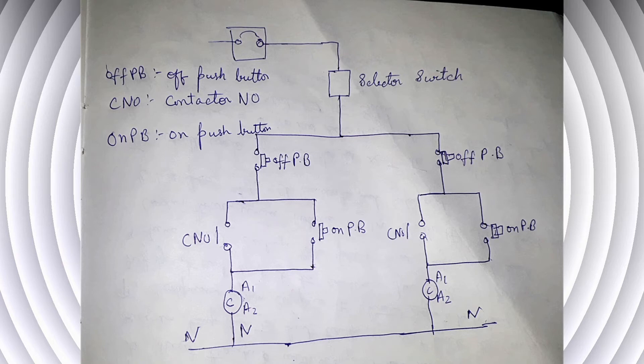To A2 of the contactor, neutral is connected — completing the wiring of pump 1. For pump 2, the wiring is similar: from the selector switch to the OFF push button, from the OFF push button one wire to the NO of the contactor and another to the ON push button. From the ON push button, one wire connects to the NO of the contactor and another wire connects to A1 of the contactor, with neutral connected to A2. This is how the control wiring is done.